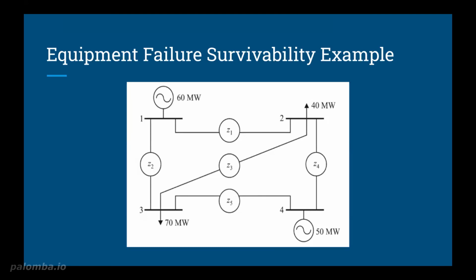Several scenarios can be conceived which would perform better than the traditional approach. So we're modeling this system in MATLAB. We will first be simulating a bad data example similar to what was done in homework 3. 5 meters are installed to measure the power flow through each of the lines. And we've started simulating this in MATLAB to identify the bad measurement. And then we're gonna postulate a failed CT and show that it could be possible to survive a failed CT event.